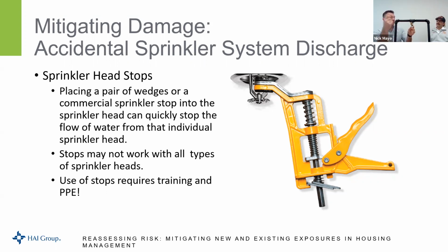Now I can attest to this, and so can Paul. If this sprinkler head is flowing, it's not an easy job. It's not an easy job, and the amount of water that's coming out of the sprinkler head, it feels like you're underneath a waterfall. So it's extremely important that between knowledge, experience, and training, if you were to stop the flow of water from a sprinkler head, even with a device like what's on your screen, I have it in my hand now, it's called a shotgun. It's a ratcheting cam style device that if water is flowing, I can put the device into the sprinkler head opening, squeeze the lever, and now that water is pinched off inside this sprinkler head, and this one sprinkler head is in theory plugged up, okay?